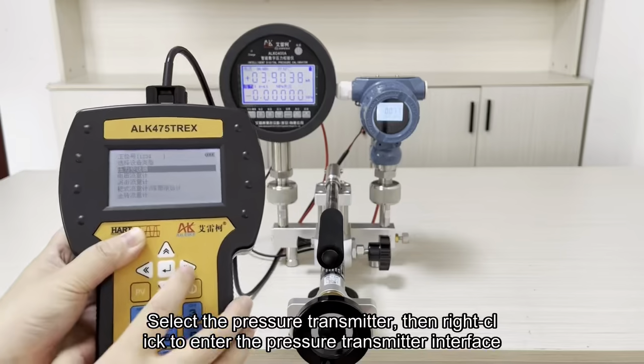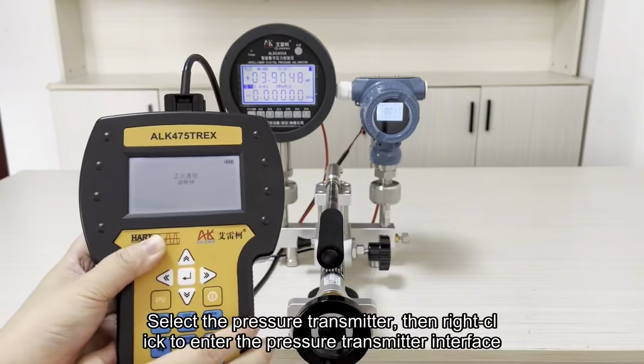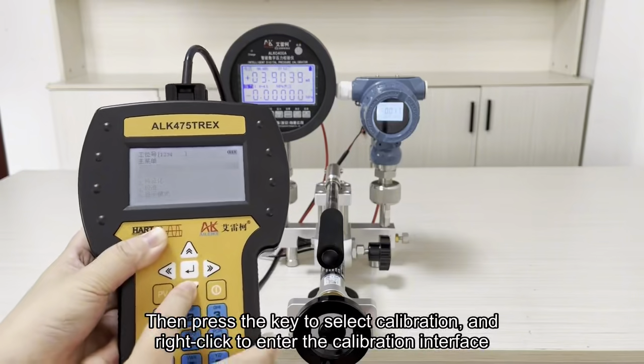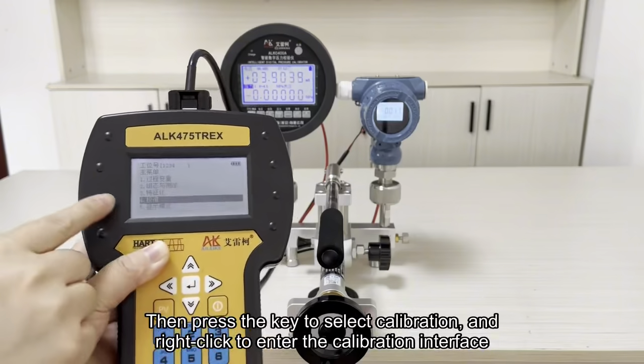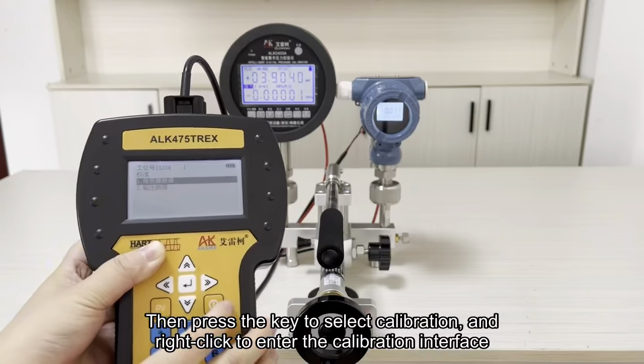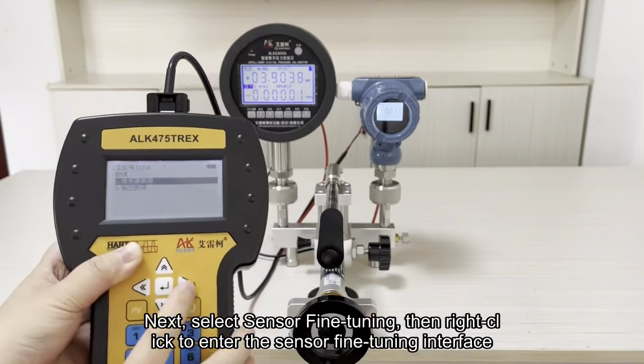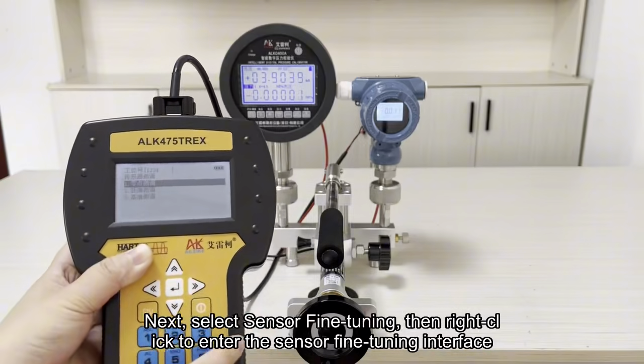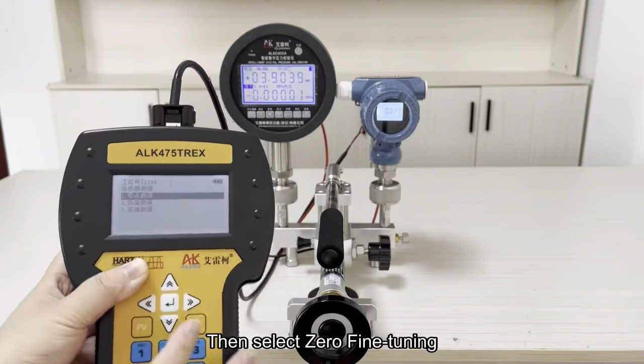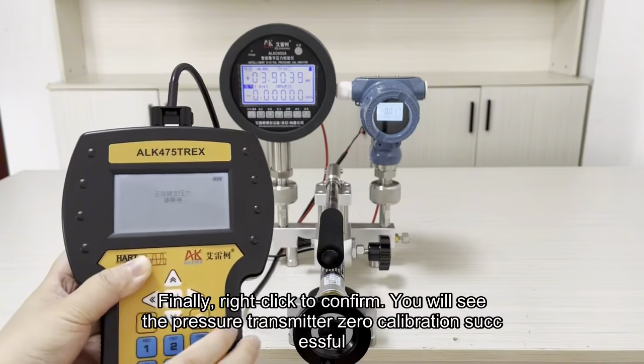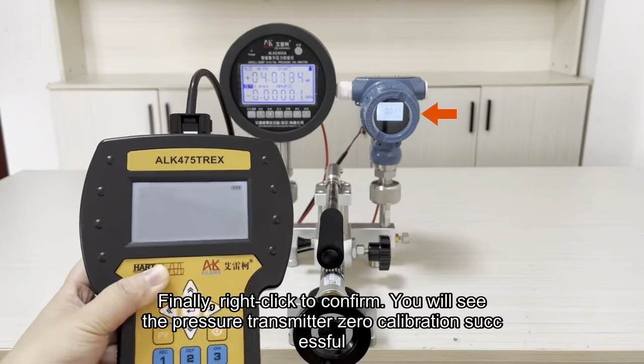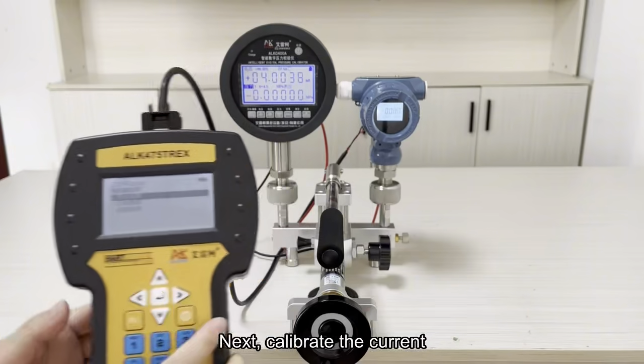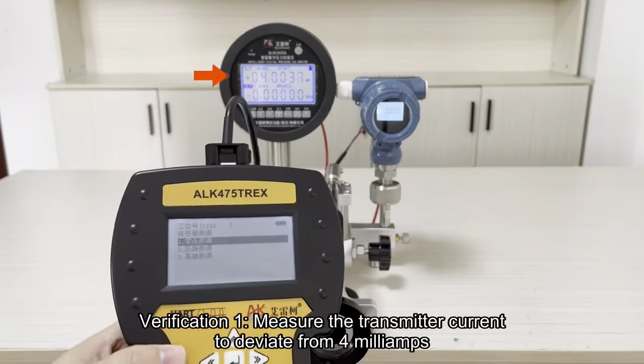Next, select the pressure transmitter, then right-click to enter the pressure transmitter interface. Then press the key to select calibration, and right-click to enter the calibration interface. Next, select Sensor Fine-Tuning, then right-click to enter the Sensor Fine-Tuning interface. Then select 0 Fine-Tuning. Finally, right-click to confirm. You will see the pressure transmitter 0 calibration successful.